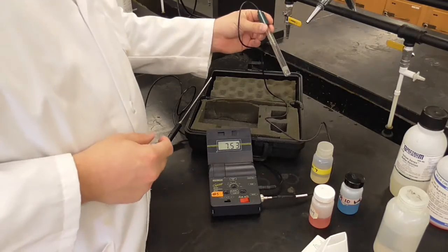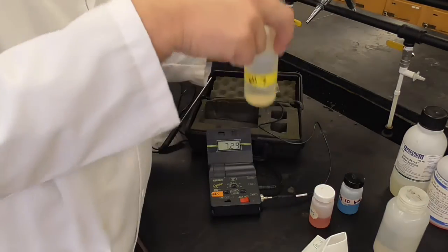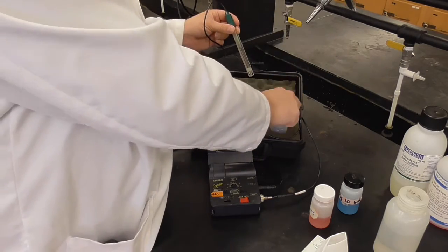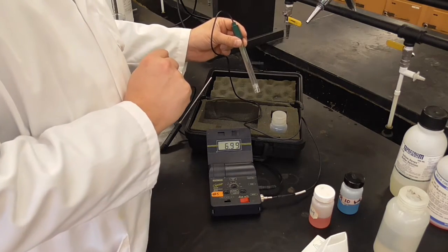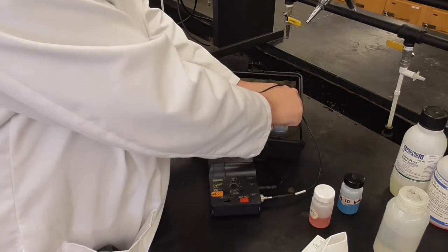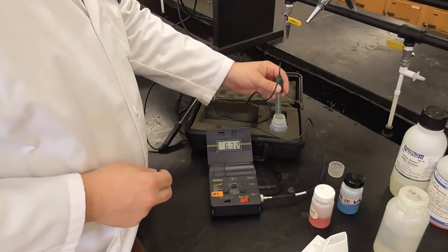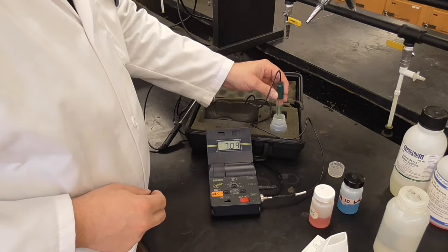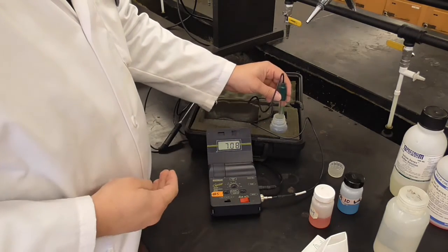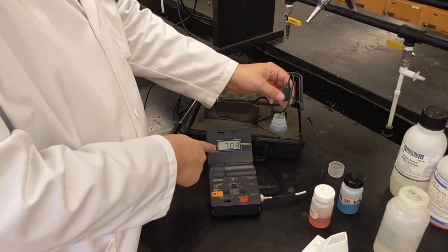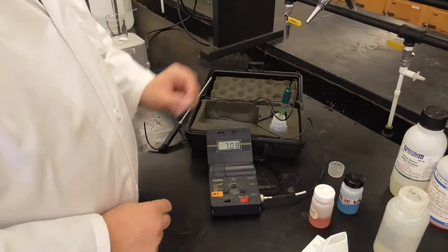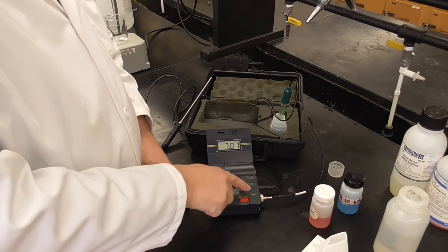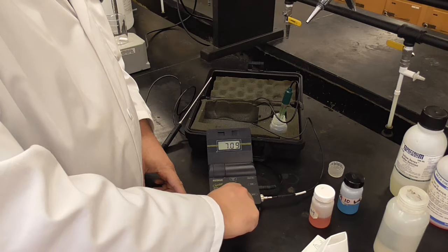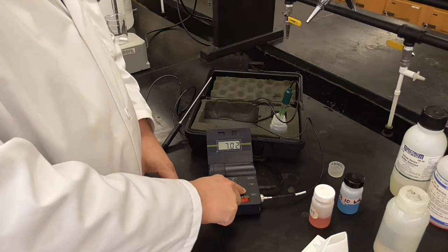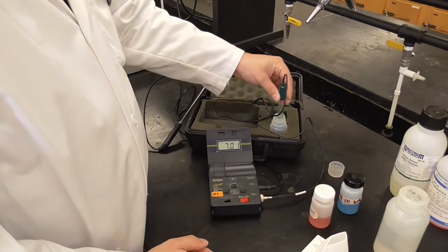Now, the first buffer we stick it in to calibrate is the pH 7 buffer, which is the yellow. I find that these little places here in the case for the pH meter hold these, because if you don't, they tend to tip over because this is kind of top heavy. So I put this in here. Now you've got to move this around a little bit. Make sure that you get the solution around that probe, and you can see that it's reading roughly 7, but not exact. So I use the calibration button, and it has grooves in it, so you push down on it from the top and turn with your thumb or your finger, and you want to get that so that it reads 7.